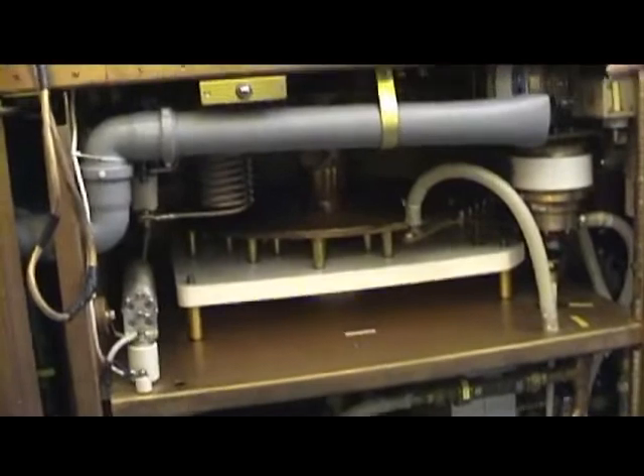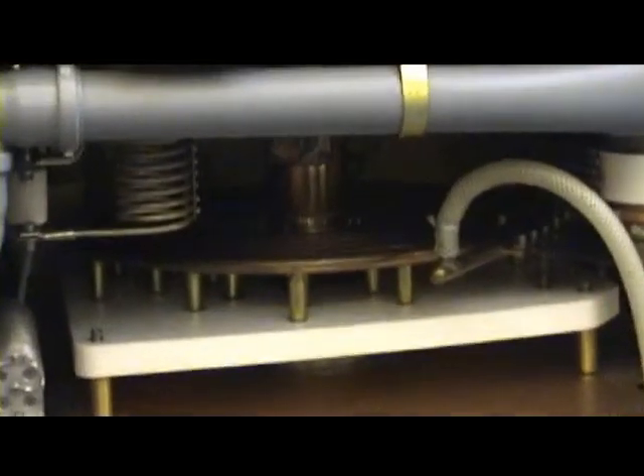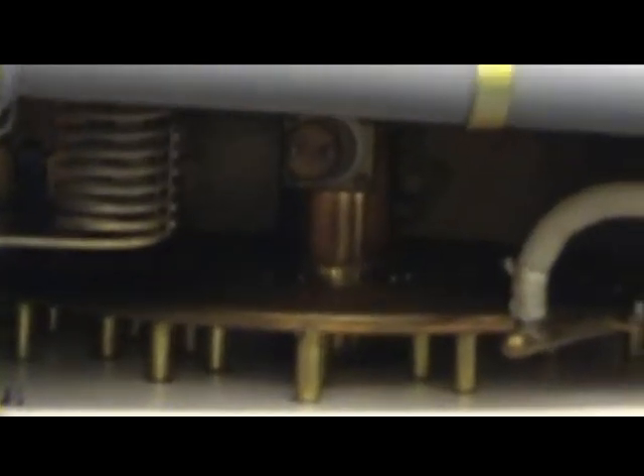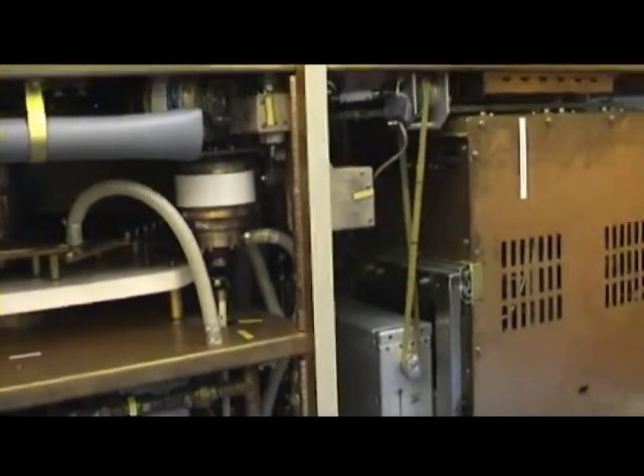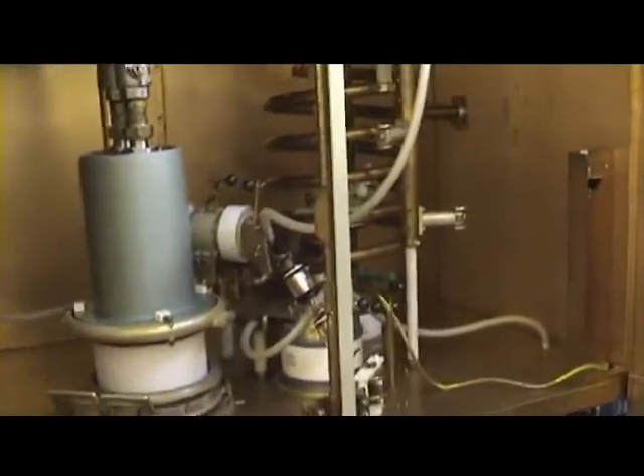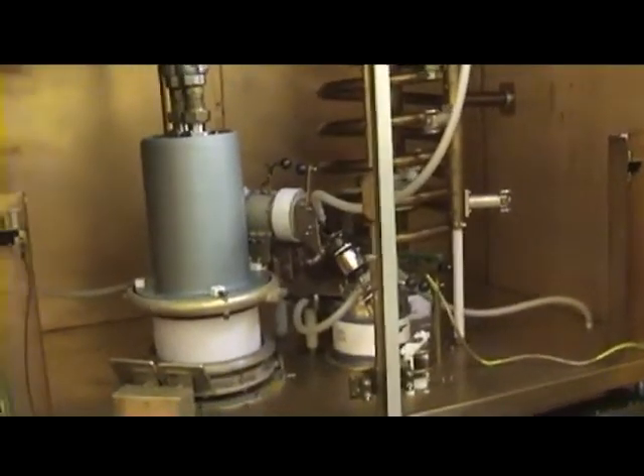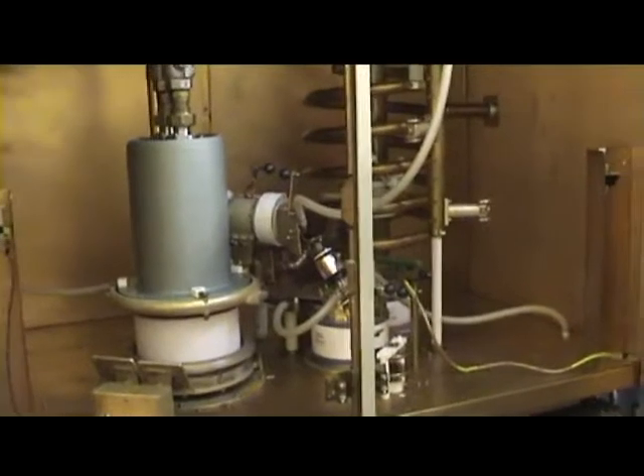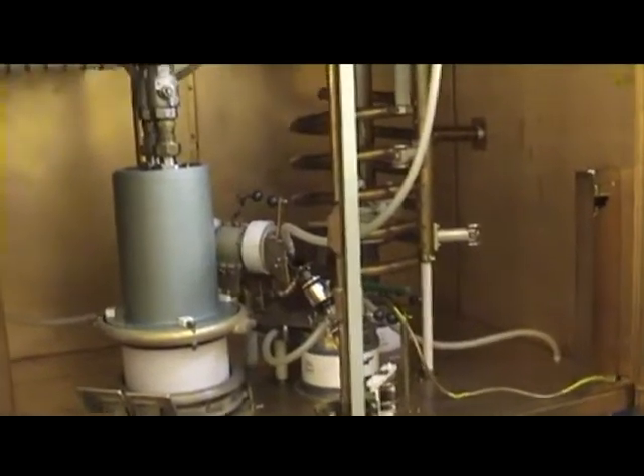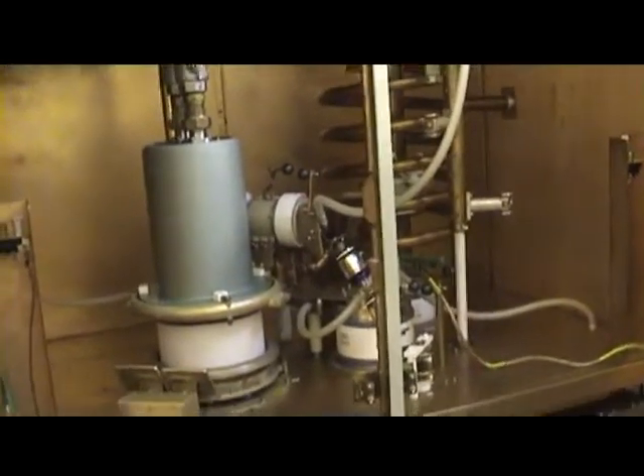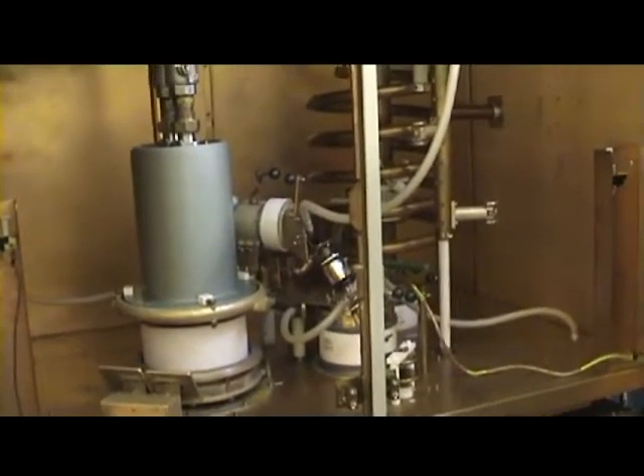The grid circuitry is absolutely industry standard now. Matching on a coil very much like a gramophone. A needle underneath there just picks up the correct amount of inductance. You can see bits of air blast cooling. You can see water flow. And then the drive belts for the capacitors from the motors below or motorized inductors. So that's the setup of the RF stage. Fairly capacious. They don't make it jammed in like on the Marconi. There's lots of room to get humans in there to do work.